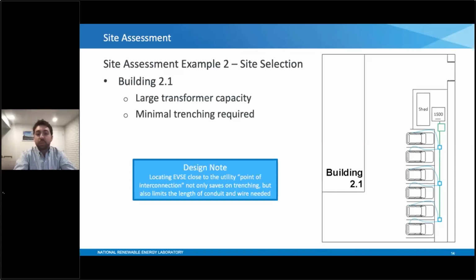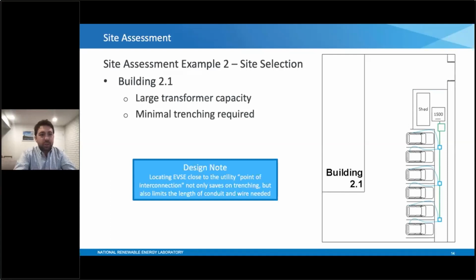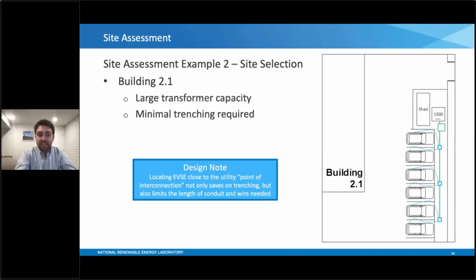Minimal trenching is required because if we do install a new service right next to the station, as opposed to trenching underneath the parking structure from building 2.1 to pull off the existing service panel, then we're not going to have as much of a trenching cost. And that's just what this design note says here. We're locating EVSE close to the utility point of interconnection. So that's where the last piece of utility equipment meets the first piece of facility equipment. Not only does it save on trenching, but it also limits the length of conduit and wire needed.